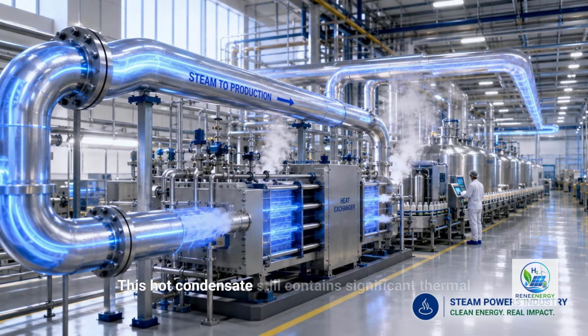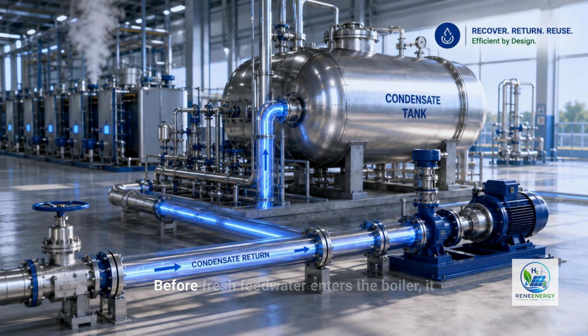This hot condensate still contains significant thermal energy and has already been treated to remove impurities, making it ideal for reuse. Returning condensate reduces water consumption, lowers fuel requirements, and improves overall plant efficiency. Instead of beginning the heating process from cold water again, the system continuously recycles its own energy, creating a highly efficient closed-loop process.